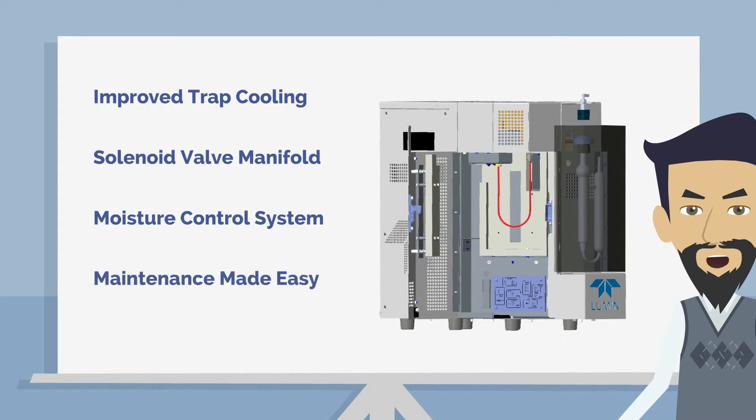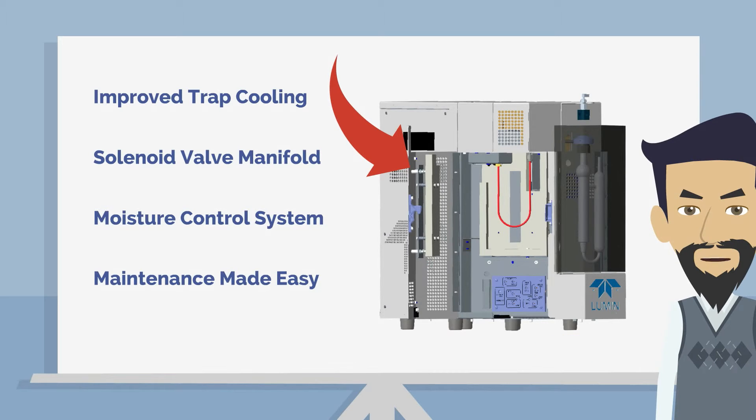The Lumin is also designed to shorten maintenance tasks that labs perform most often. Full access to the analytical trap and solenoid valve manifold are as simple as opening a door. Thanks to our clever trap compartment, both analytical trap nuts can be easily accessed. This makes for quick, easy trap changes, reducing downtime.